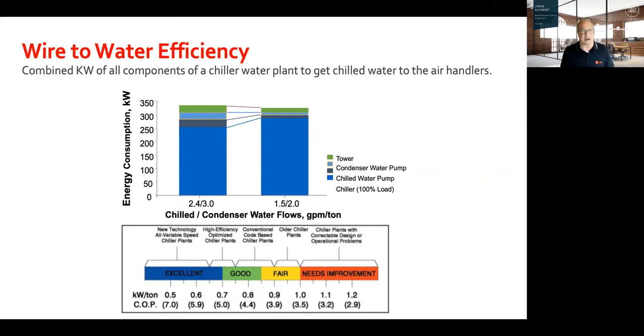There are the other components that are left, with the tower water pumps, the building load actually, and condenser water pumps and fans to squeeze that little bit of extra energy out of your chiller plant. The bottom part of that graph talks about a good kW per ton plant. You can't get through a training presentation without talking about kW per ton. So that's really the wire to water efficiency that we speak about. A good water-cooled chilled water plant, or excellent actually, is running in the 0.6, 0.7 kW per ton range. That includes all the pumps, the tower fans, the chiller itself. A good one is 0.7, 0.8, 0.9 is not even bad when you consider an air-cooled system runs about 1.7 or 1.8 kW per ton.